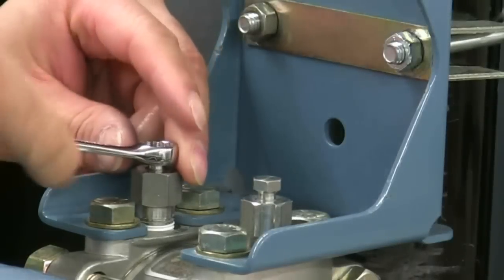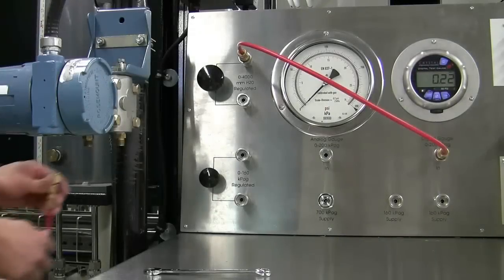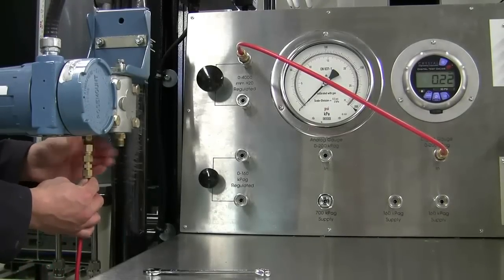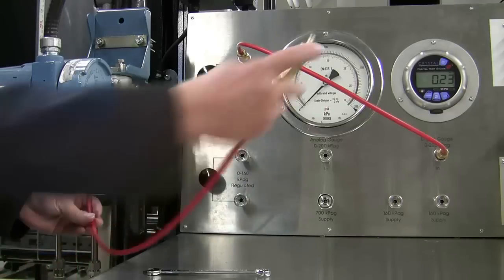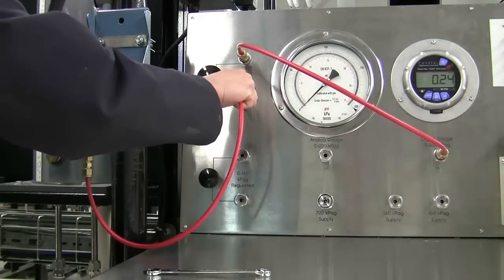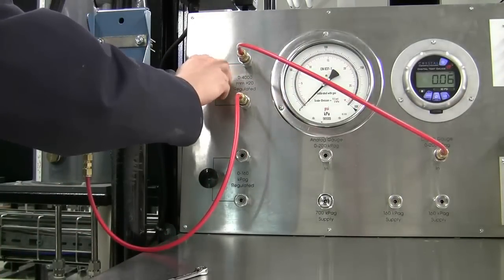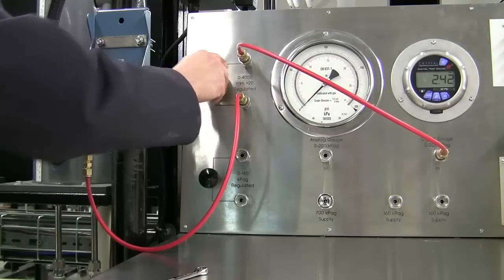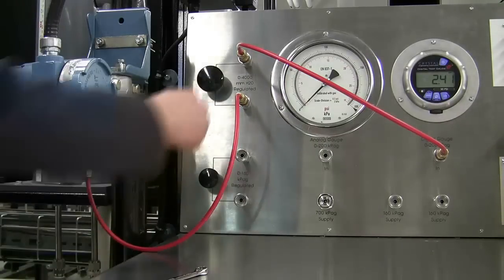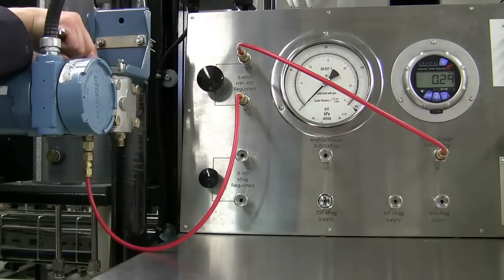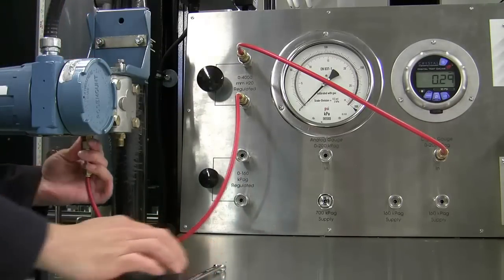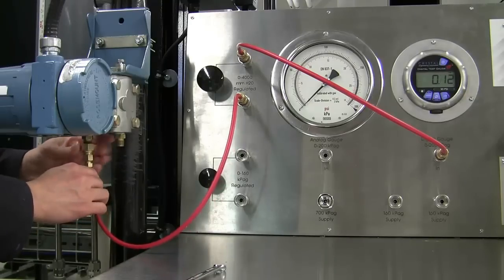The next step is to clean and dry the DP cell. Begin by opening both bleed valves on top of the transmitter. This will allow any trapped water to drain out of the transmitter. Connect the tubing to the high side of the transmitter. You only need to hand tighten the fittings for now. Once the tubing is connected to the second regulator output, apply the air until you begin to hear a hissing sound. Let the air dry the high side of the DP cell for a few seconds. Then remove the air and close the bleed valve. Repeat these steps for the low side of the DP cell.